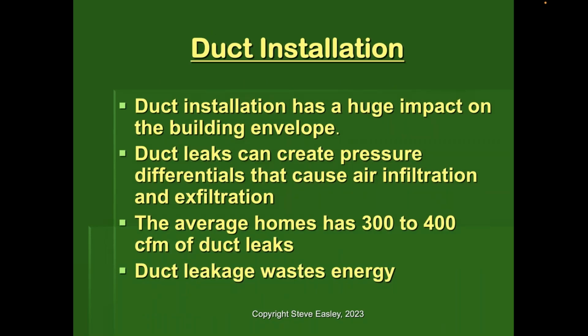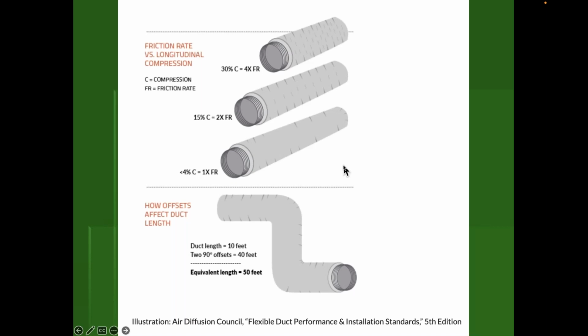Duct insulation has a huge impact on overall performance. Duct leaks can create pressure differences that create air infiltration and exfiltration across the building envelope. Like I said, it's not uncommon to have 300 to 400 CFM of duct leaks, and duct leakage, of course, wastes energy.